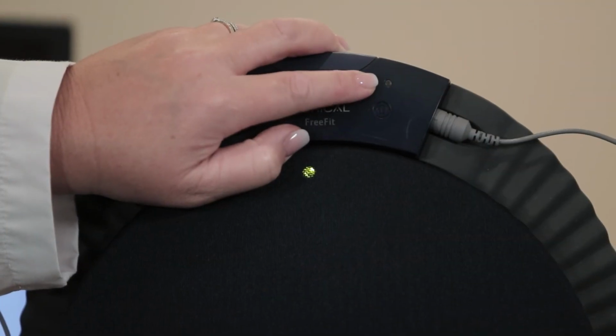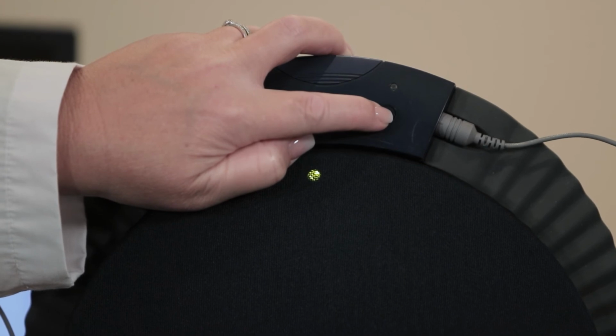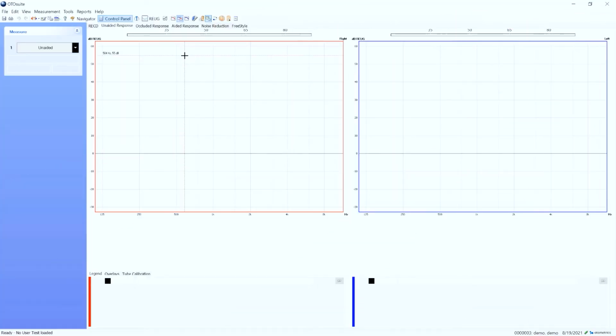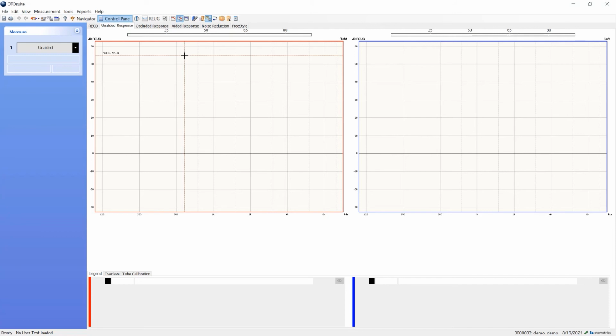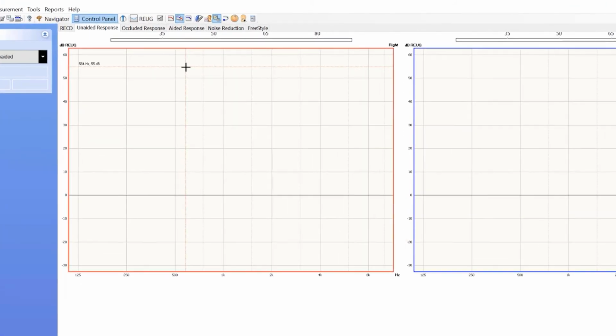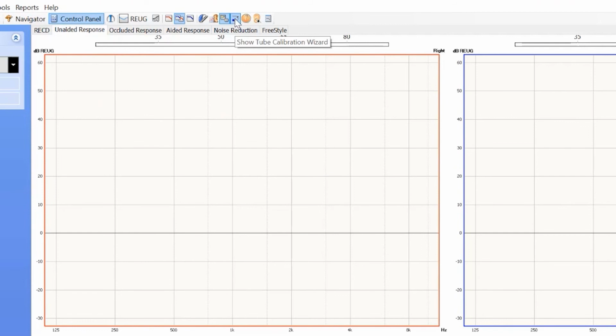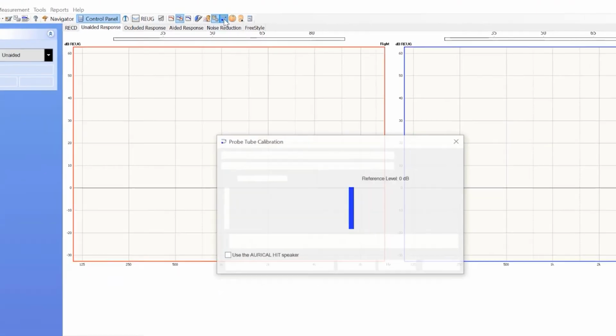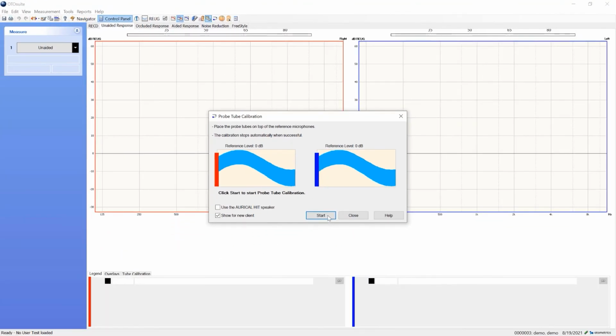Open the probe tube calibration wizard in OtoSuite by briefly pressing the power button on the collar. Or, as shown here, you can open the wizard from the software. The icon is on the right side of the toolbar. It looks like a probe tube with a blue handle. To begin probe tube calibration, you can press the Start button in the software screen as shown here, or tap the Power button on the free fit collar. Calibration stops automatically when complete, and you should see a successful calibration screen.